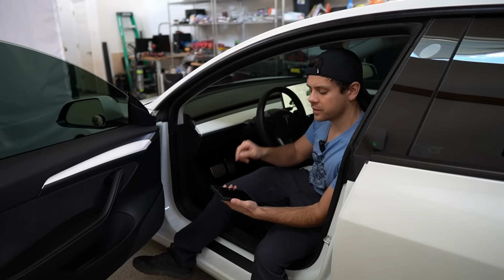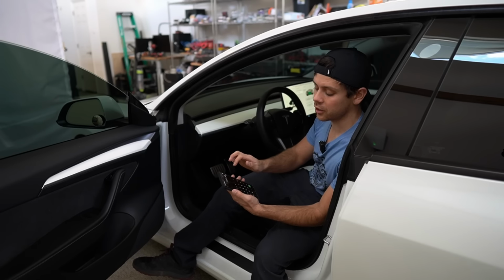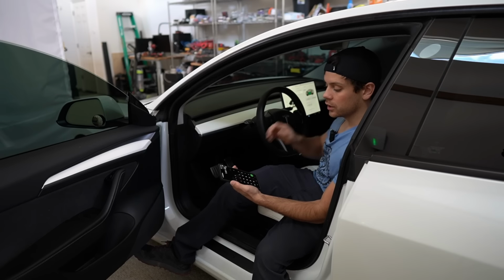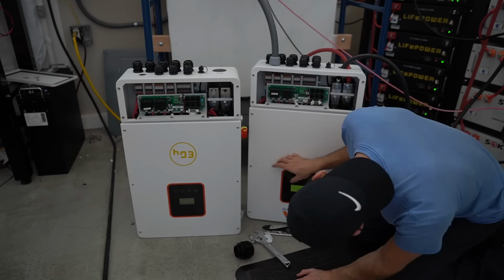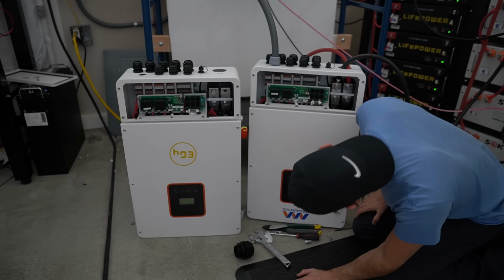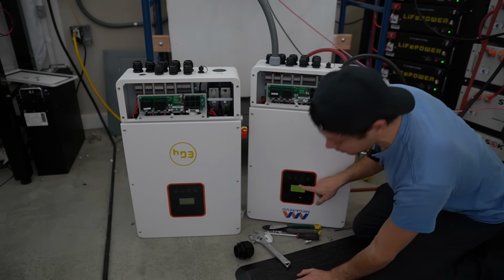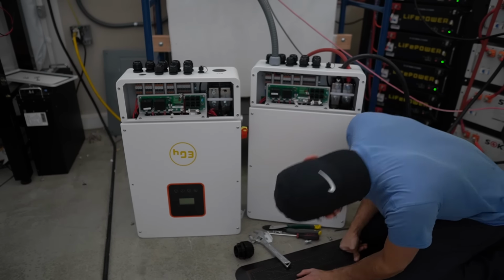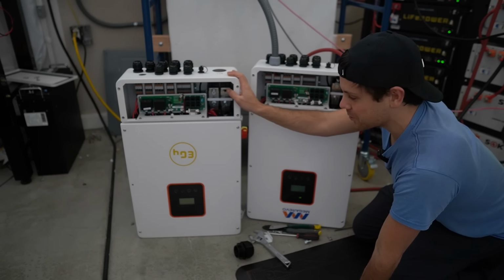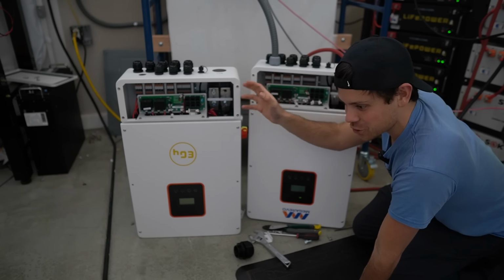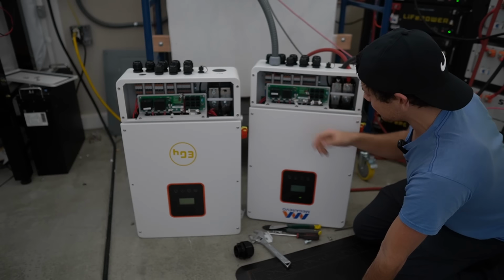We haven't had the GFCI trip, and so now we're gonna increase the current to 31 amps. Then we'll go look at the inverter and see how it's doing. We're pulling 7,700 watts. From the battery, we're pulling 8,200 watts. Now I'm wondering what is going on with this inverter. I don't know why it's tripping that GFCI, but it doesn't do it on here.